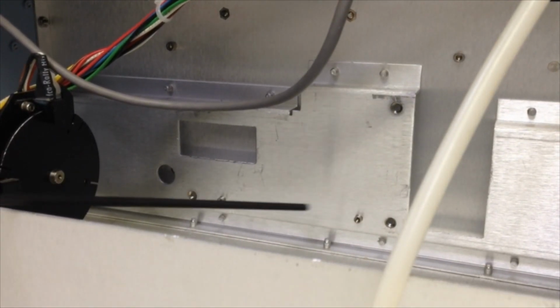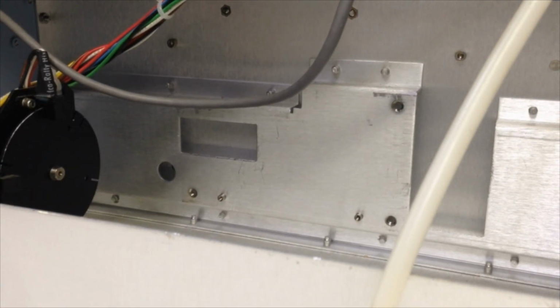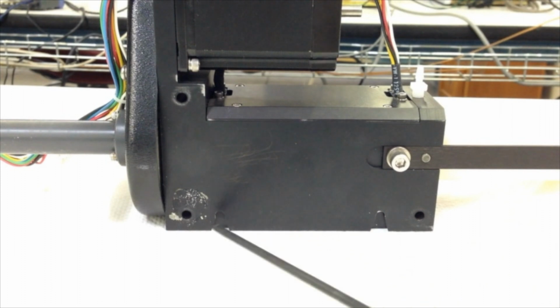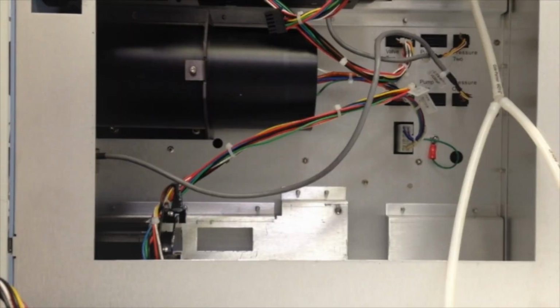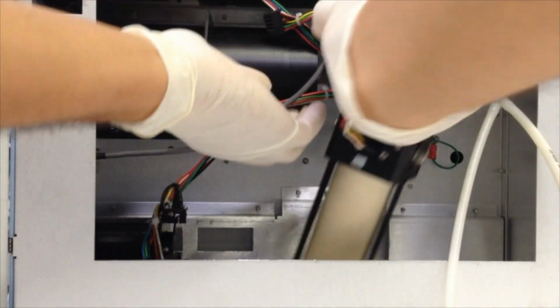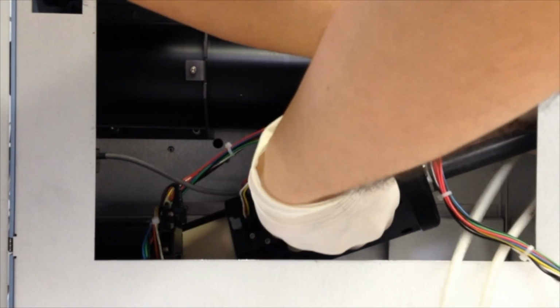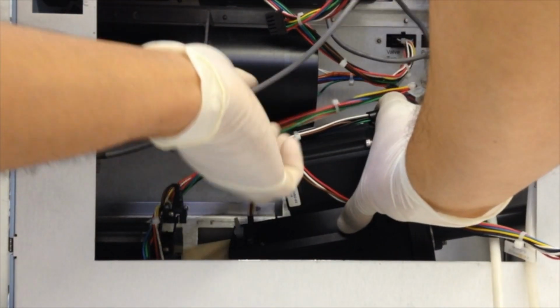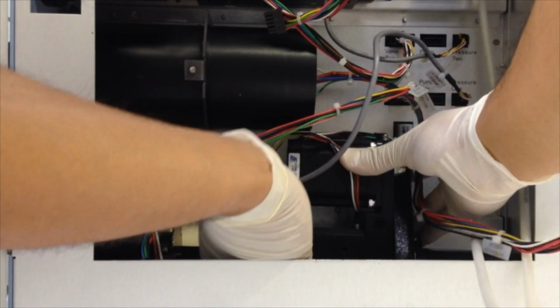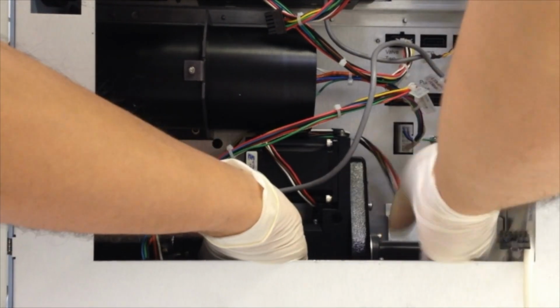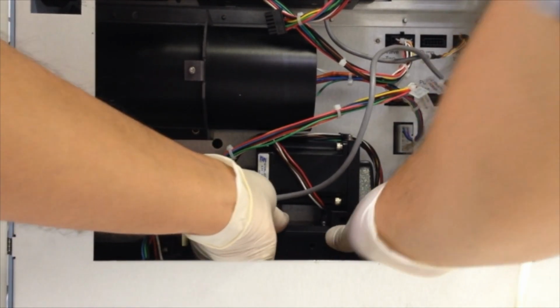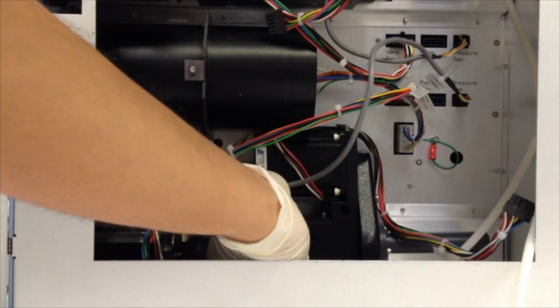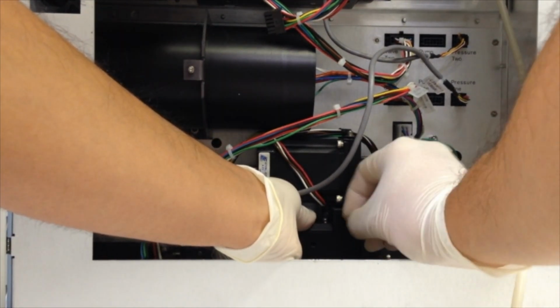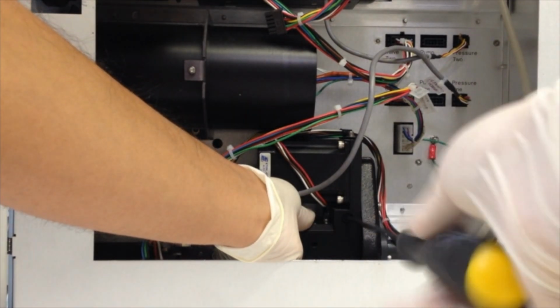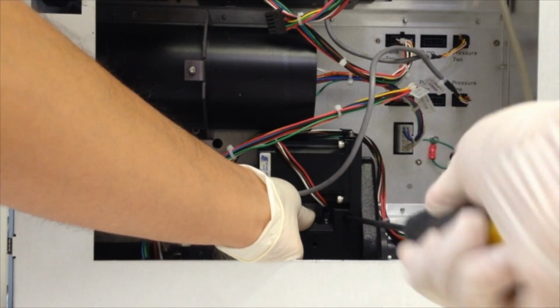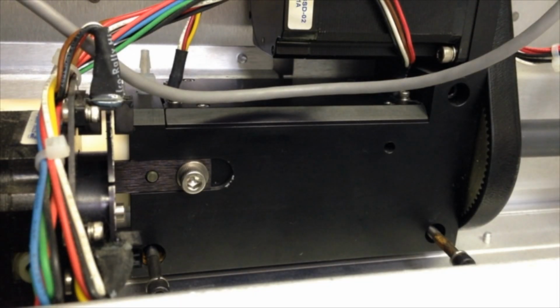The Pinnacle chassis has two brackets that go into the slots of the pump body. Place the pump back inside the Pinnacle and make sure the pump is set onto the two brackets. If the pump is in the correct position, you will not be able to move the pump back and forth. Secure the pump to the chassis with the 3 screws.